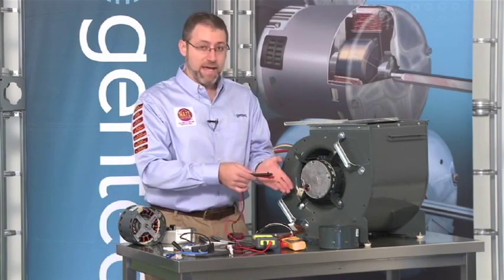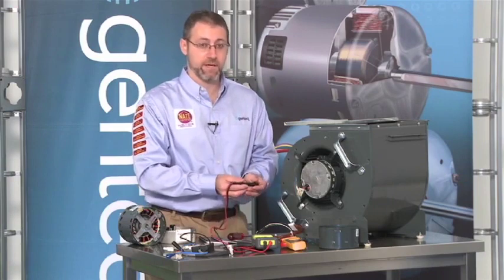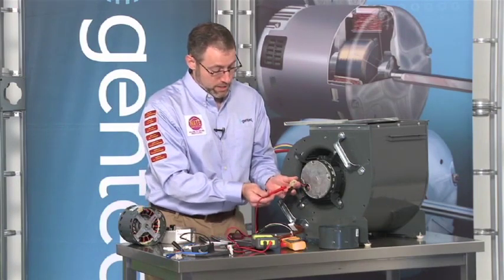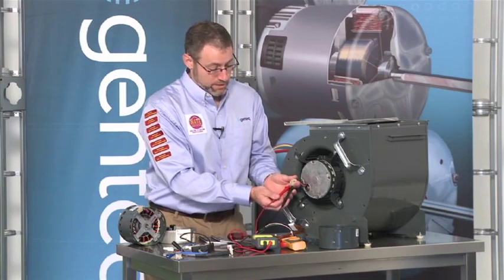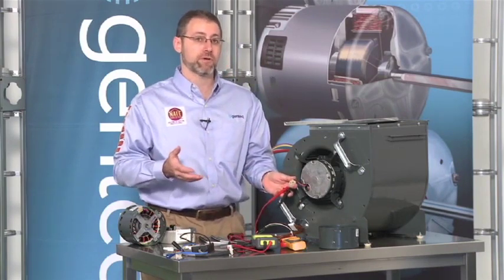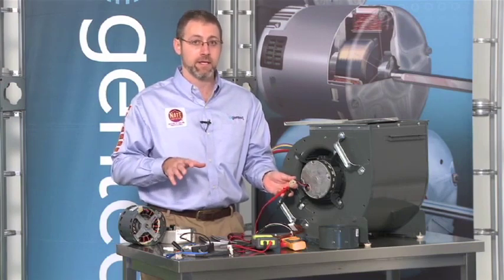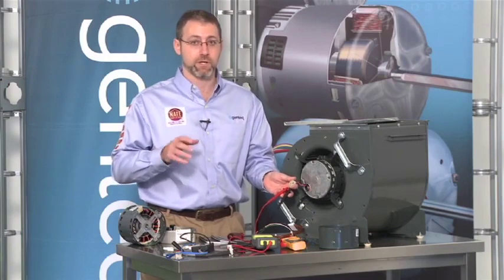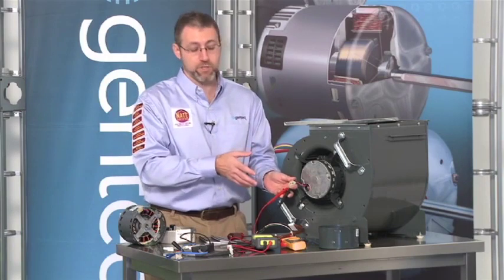So if it passes this test, the next test is the phase-to-phase test. This is where we're going to check the windings themselves to make sure they are reading the proper amount of ohms. Now, all of our motors are going to read 20 ohms or less. We don't make any ECM motors, one-third through one horse, that read more than 20 ohms. So if you read more than 20 ohms, that's a bad motor right off the bat.